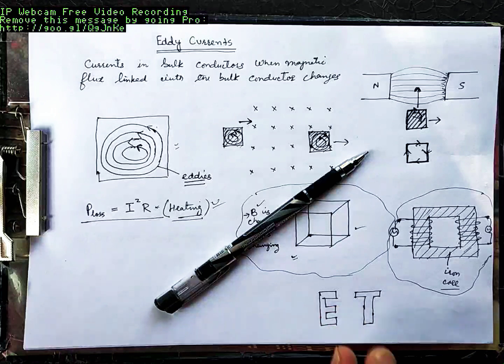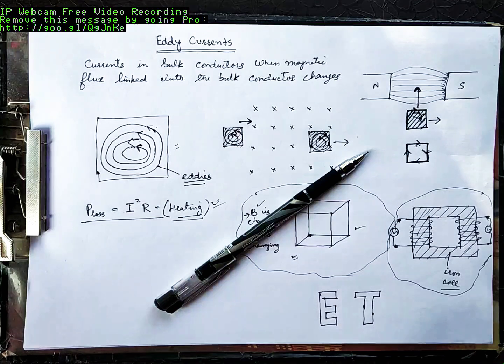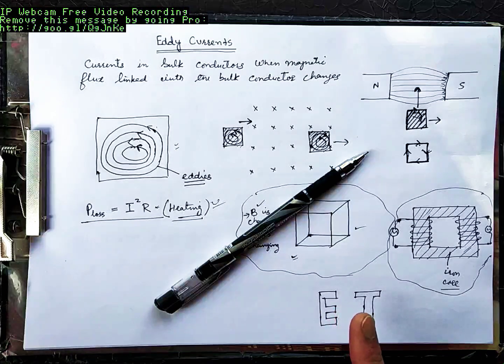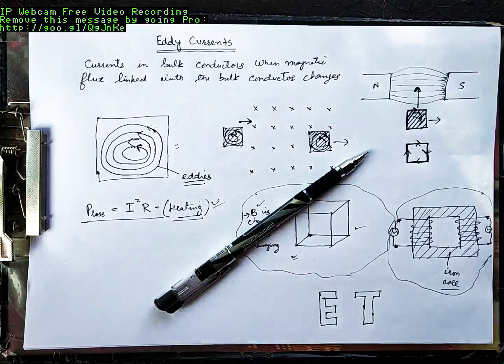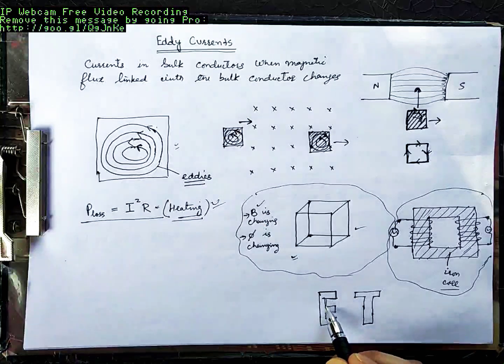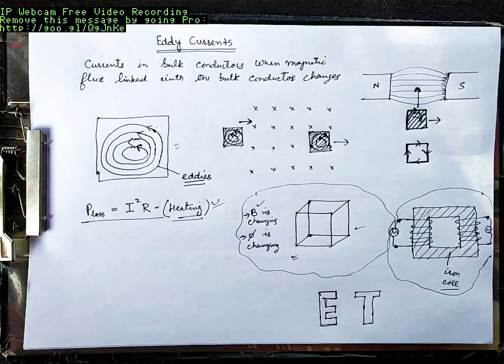And these first E, second E, third E, you call them laminations. They are electrically insulated from each other. That is, they do not have electrical contact. If they had electrical contact with each other, then making them of a single material or of separate E's would be one and the same thing. So in order to make them electrically insulated from each other, we coat these single E's with an insulating material like lacquer or varnish.